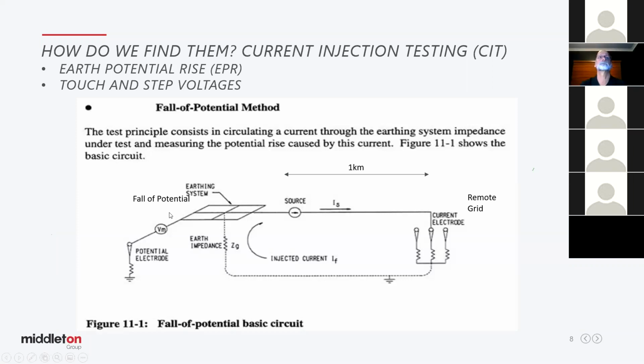As you'll see over on the left here, we can measure the voltage that we've created, the EPR that we've created at this substation grid, by measuring the voltage between the grid and this reference electrode out at remote earth, or 0 volts. Indeed, to get those graphs that we've seen earlier, where it falls away from the substation, we'll take a number of measurements along the ground, potentially up to 1 kilometre away from the substation under test, to get a nice EPR curve rather than just a single voltage measurement.